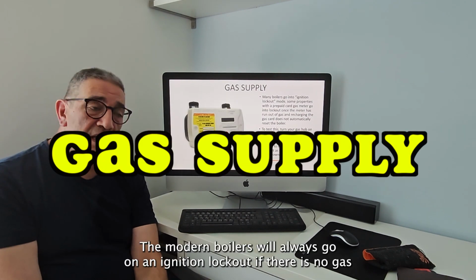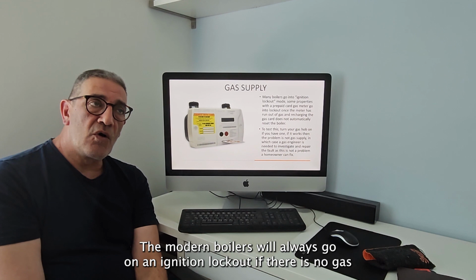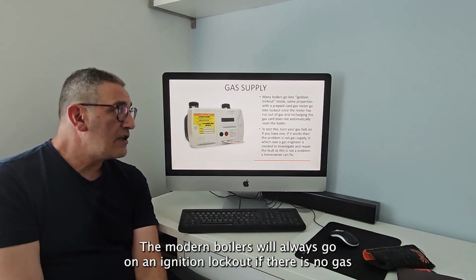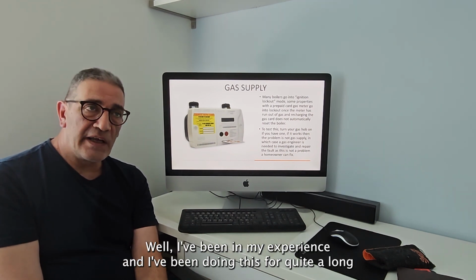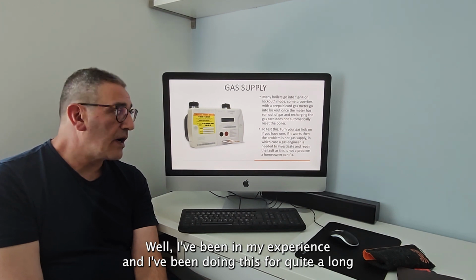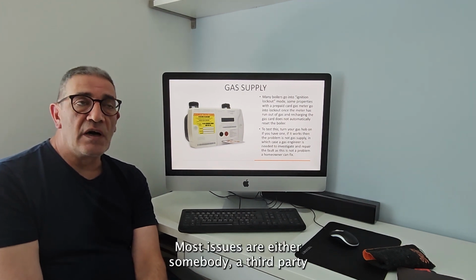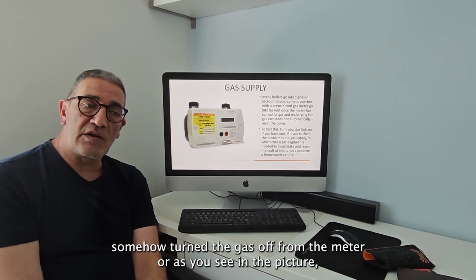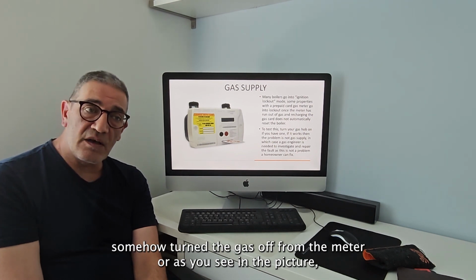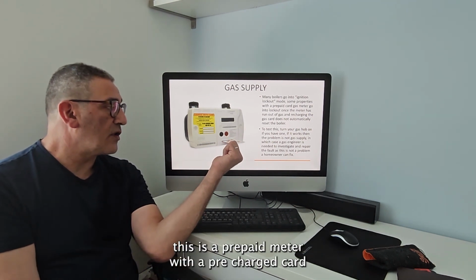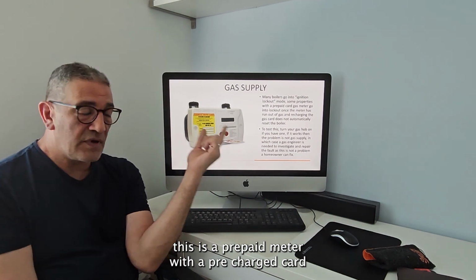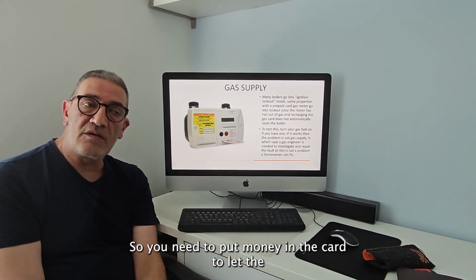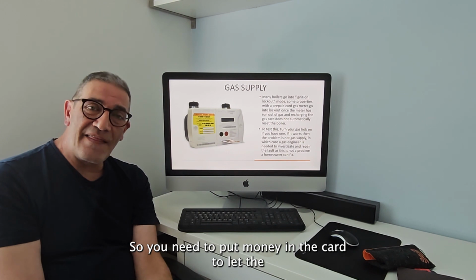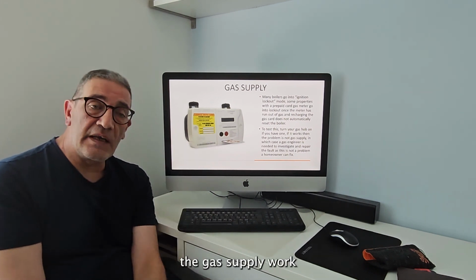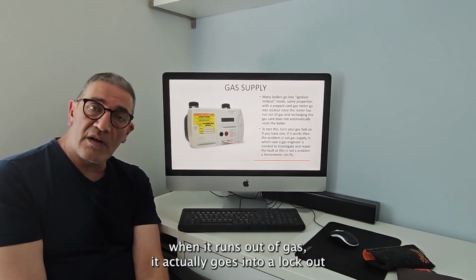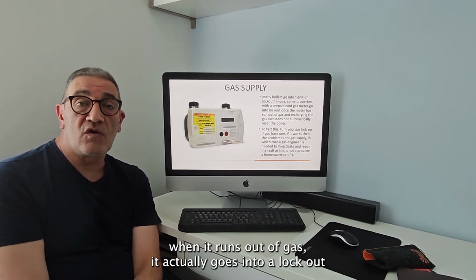Gas supply. Modern boilers will always go on an ignition lockout if there is no gas. In my experience, and I've been doing this for quite a long time, most issues are either somebody, a third party, somehow turned the gas off from the meter, or, as you see in the picture, this is a prepaid meter with a pre-charged card, so you need to put money on the card to let the gas supply work. When it runs out of gas, it actually goes into a lockout.